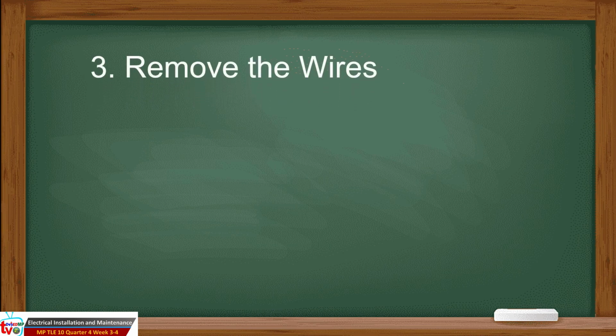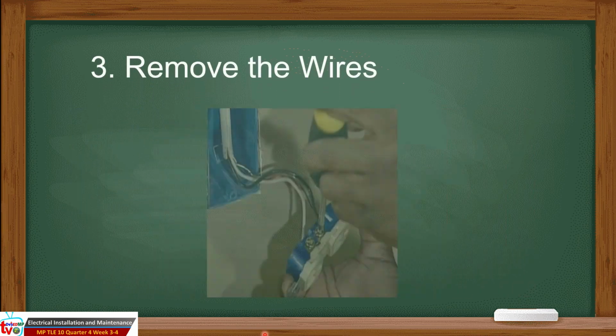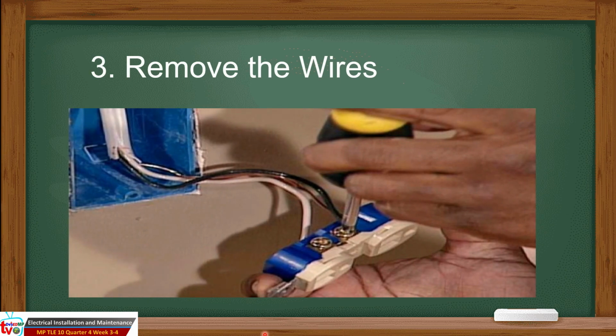Remove the wire. Remove the mounting screw and take the outlet from the wall. Remove the wires from the outlet in the following order, starting with the black hot wire. Loosen the screw by turning it counterclockwise. Then do the same to remove the white neutral wire, and lastly the ground wire.